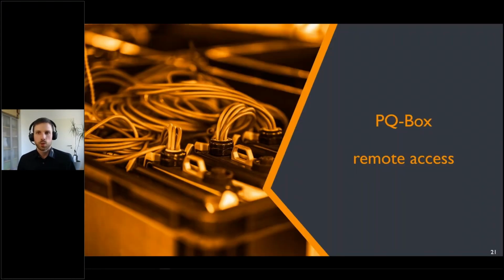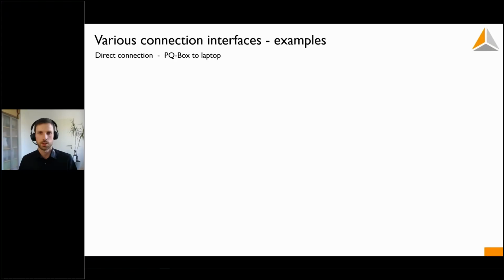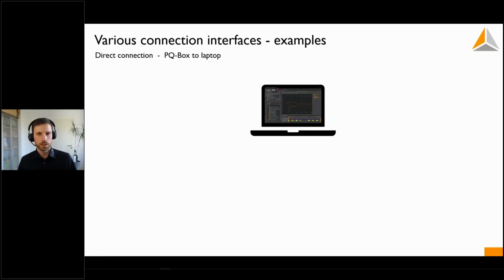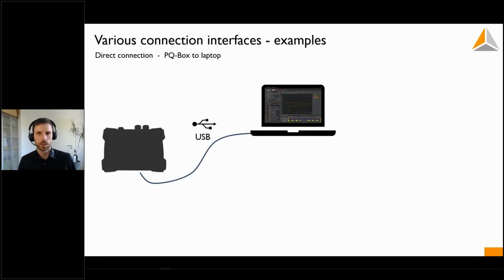Last but not least, I will talk about how to remotely access the PQ-Box. So the PQ-Boxes, they all have different interfaces. So let's connect several PQ-Boxes to my laptop. So I go in this example with a direct connection. This means from device to device. The easiest way is, well, take the USB cable that comes with the PQ-Box, connect it to your laptop, connect it to the PQ-Box, run WinPQ-Mobil, and it automatically detects the PQ-Box.